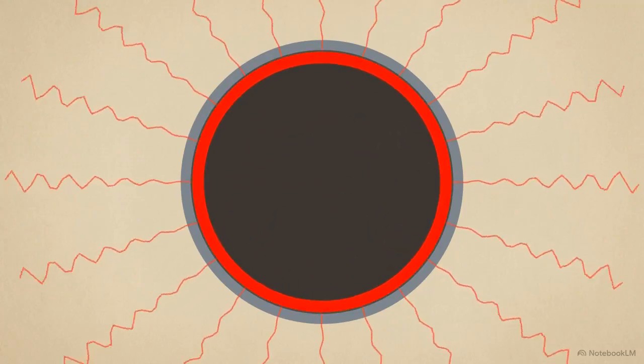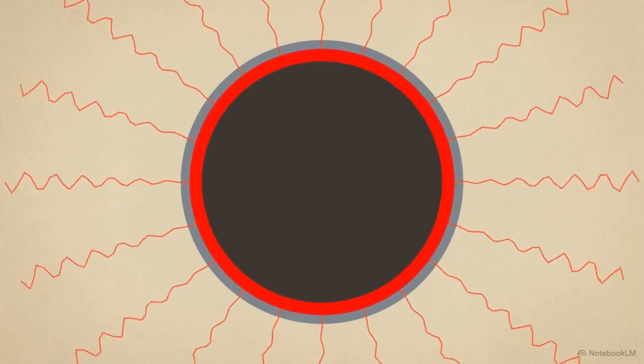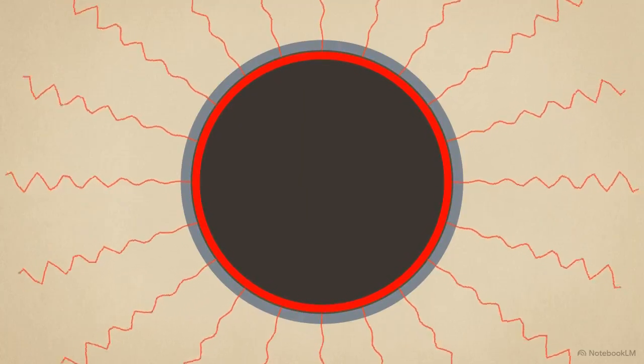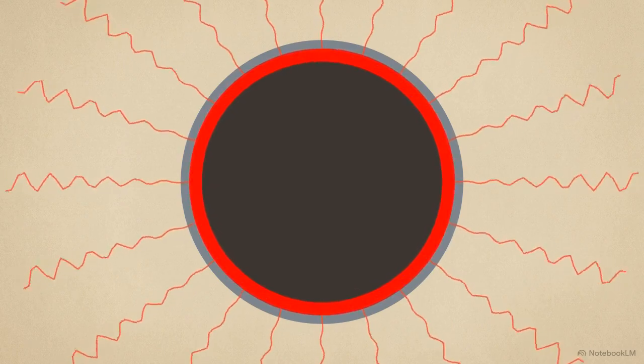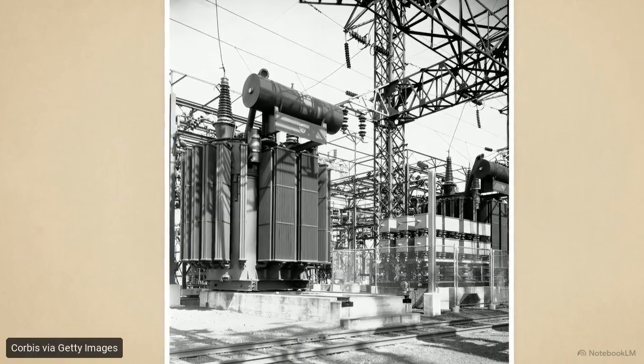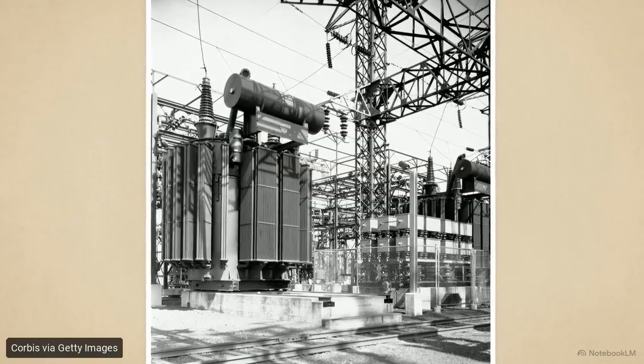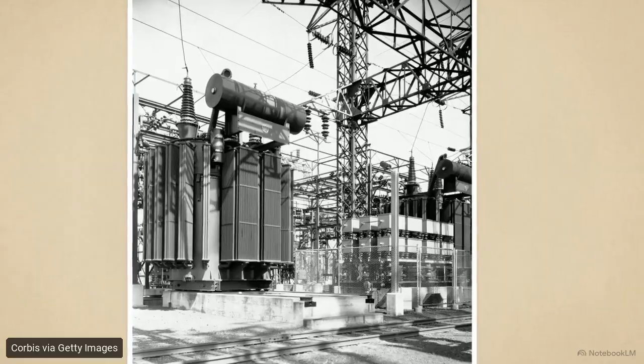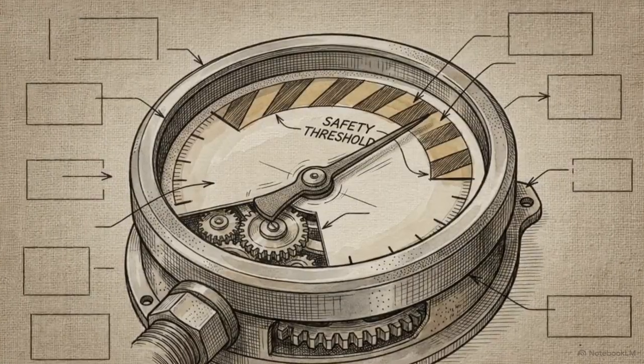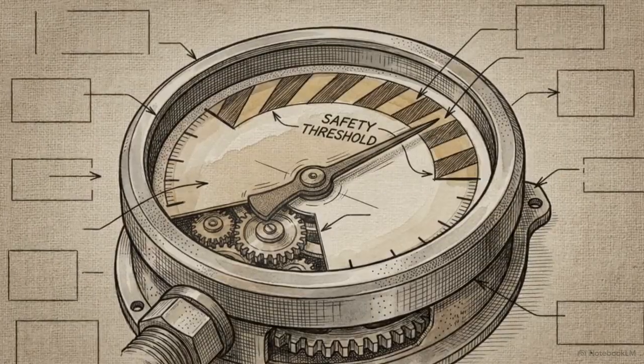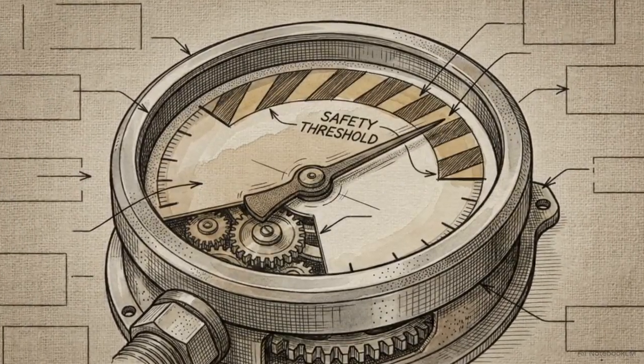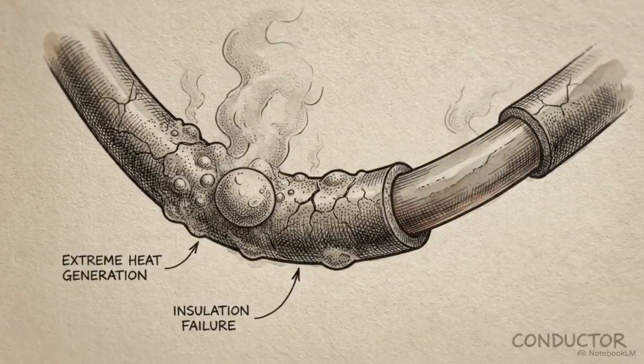This collision triggers the skin effect. Standard 60 Hz current flows evenly through an entire wire, but high-frequency harmonics are magnetically forced to the extreme outer edges. Crowding into that tiny outer sliver exponentially increases resistance, generating dangerous physical heat. This internal heating is so intense that utility companies must preemptively derate modern equipment, preventing massive transformers like the one pictured from melting down. To survive the harmonic distortion, engineers must often cap their safe operation at just 80% of their true rated capacity.